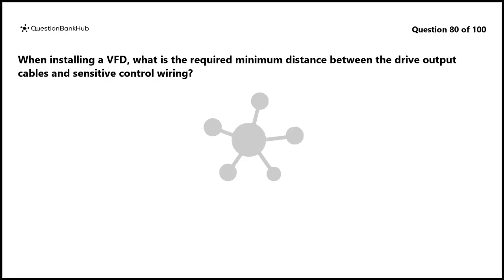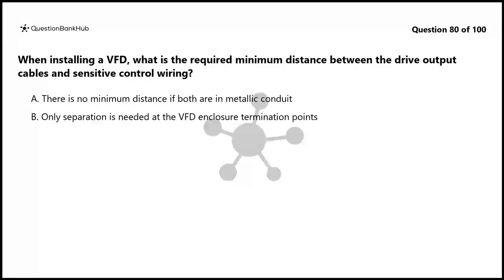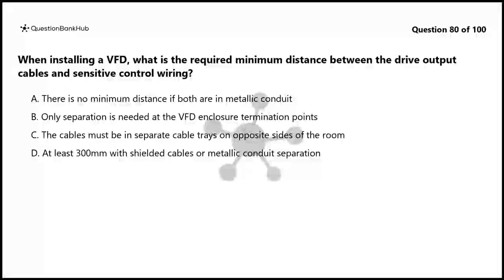Question 80. When installing a VFD, what is the required minimum distance between the drive output cables and sensitive control wiring? A. There is no minimum distance if both are in metallic conduit. B. Only separation is needed at the VFD enclosure termination points. C. The cables must be in separate cable trays on opposite sides of the room. D. At least 300 mm with shielded cables or metallic conduit separation.